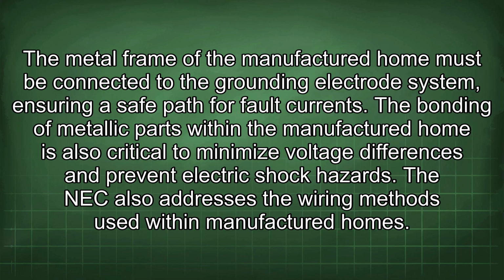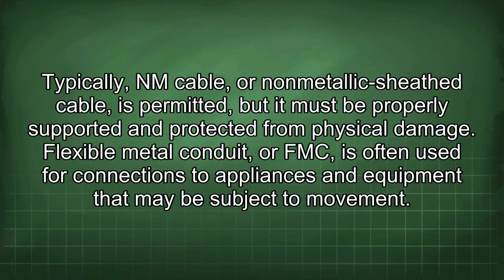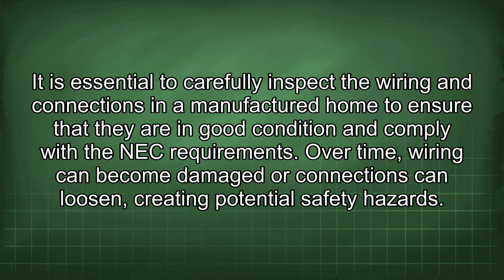The NEC also addresses the wiring methods used within manufactured homes. Typically, NM cable, or non-metallic sheath cable, is permitted, but it must be properly supported and protected from physical damage. Flexible metal conduit, or FMC, is often used for connections to appliances and equipment that may be subject to movement. It is essential to carefully inspect the wiring and connections in a manufactured home to ensure that they are in good condition and comply with the NEC requirements.